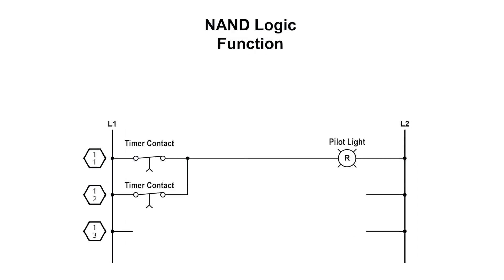The NAND function can come from a combination of the AND and NOT logic function in which two or more normally closed contacts are connected in parallel to control the load. The example shows the NAND logic in which the pilot will go off if both the timing relays are energized and done timing. If either one is not actuated and completed, then the pilot light will stay on.